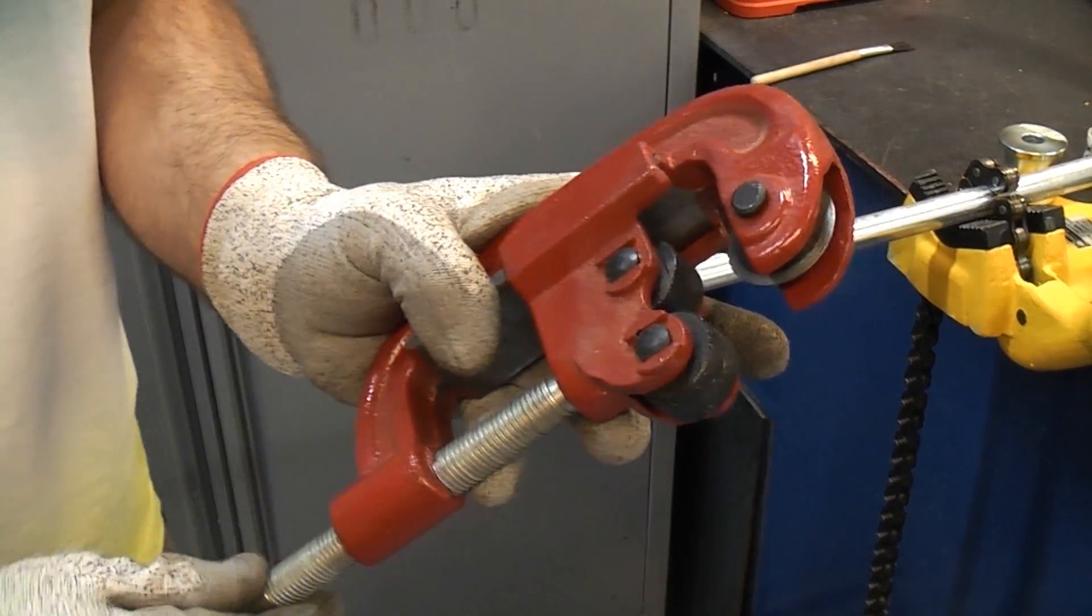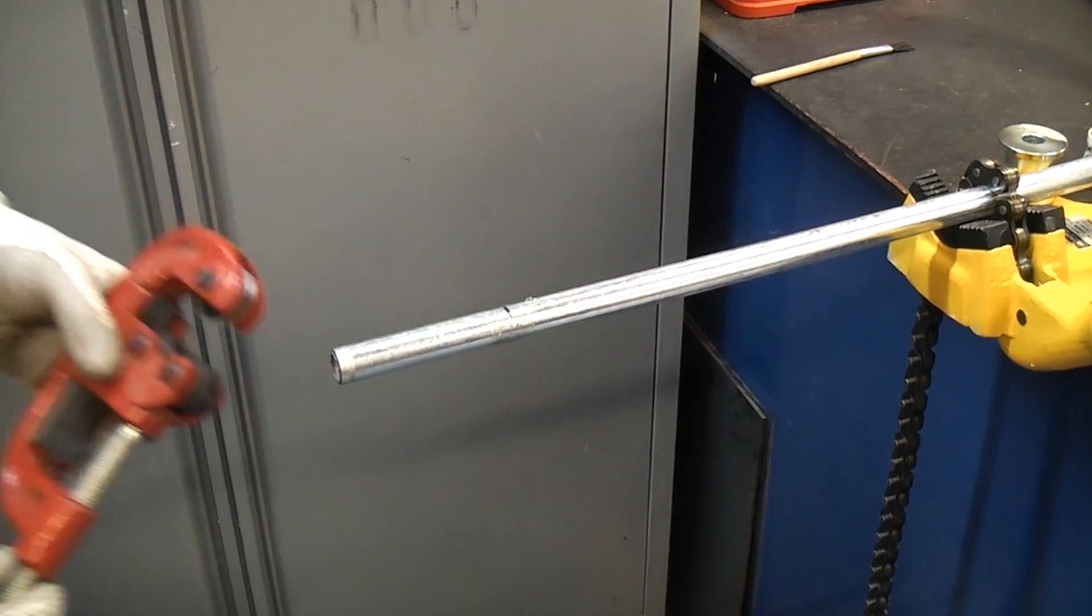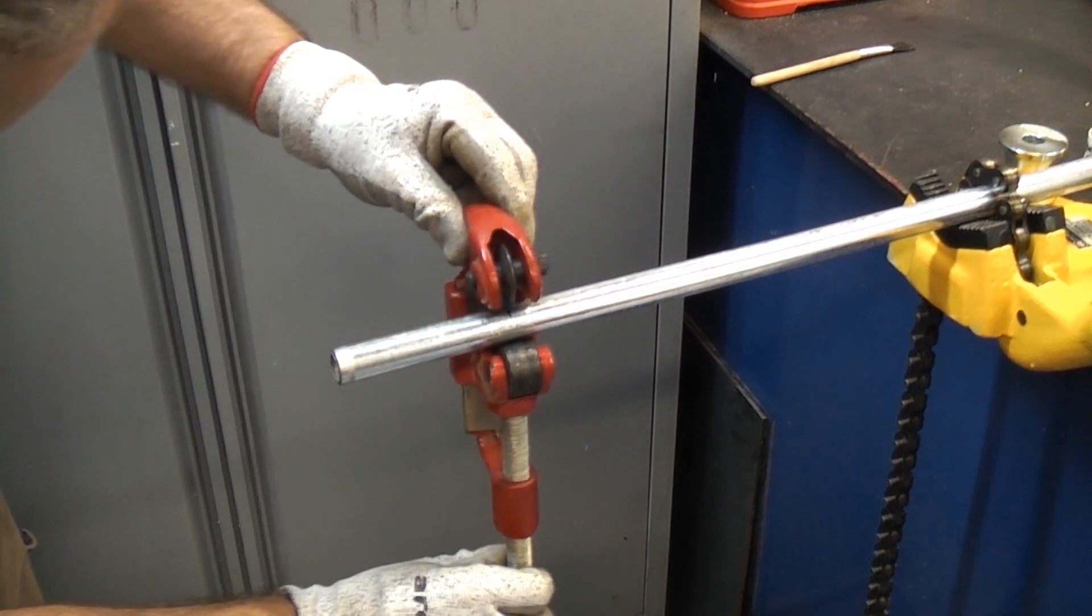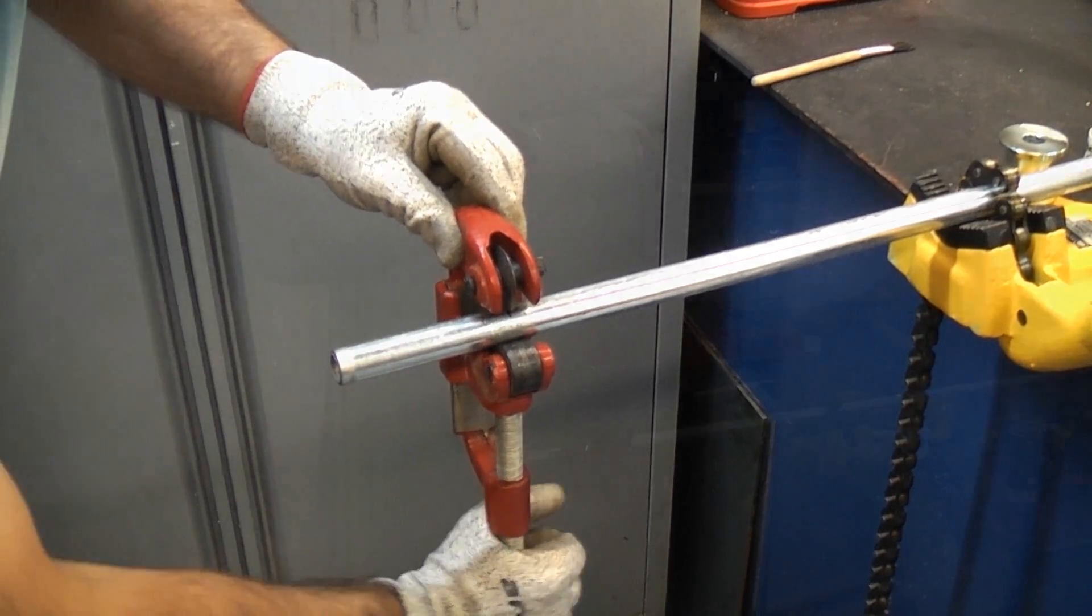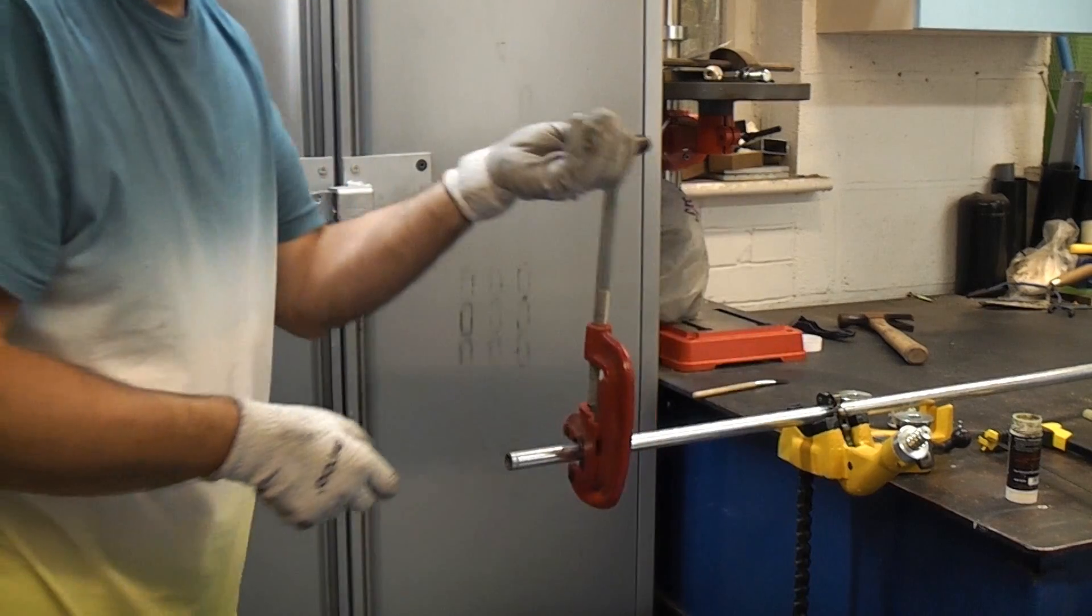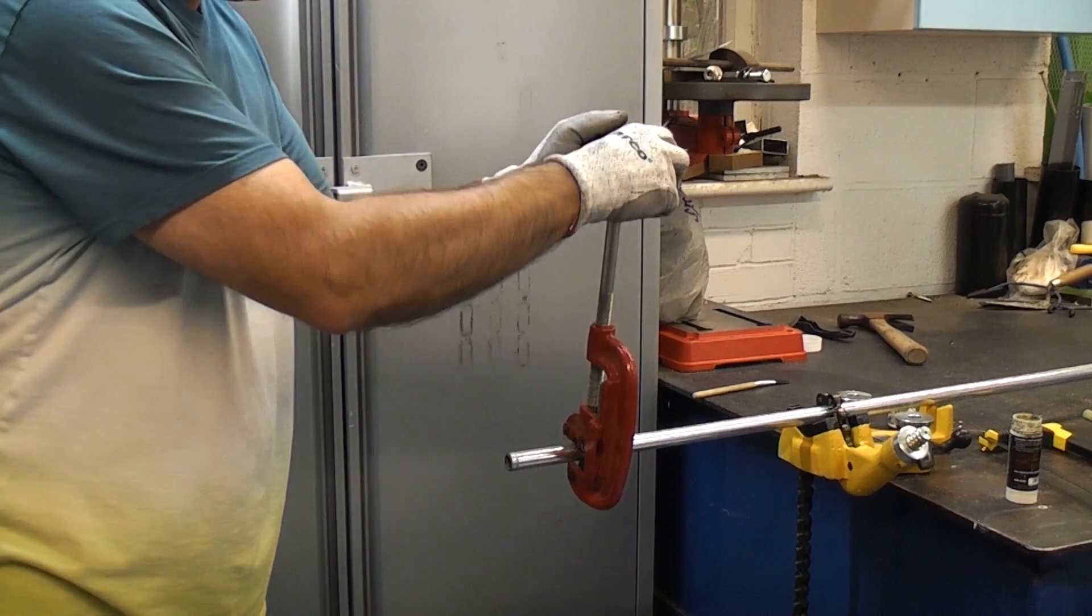So these are often used on pipe and this one will cut from half an inch up to two inches. So all we need to do is put that in the correct position and then tighten it up, and we can then start to rotate that around the conduit. Every time you do a revolution you can tighten the handle further.